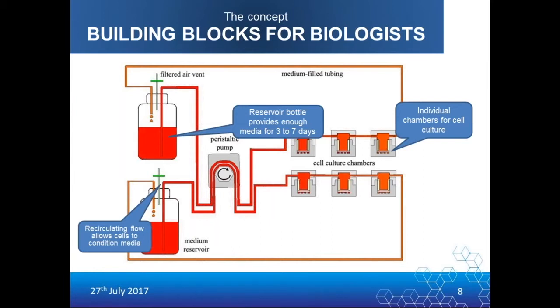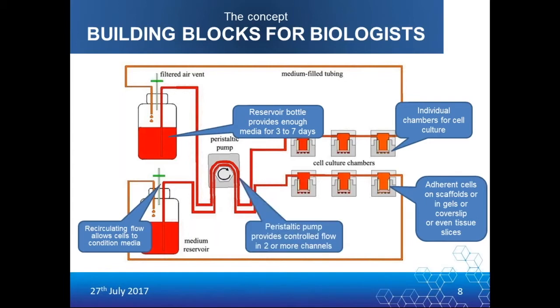These examples have 3 individual cell culture chambers per circuit. The current record for chambers in a row is 12, but the most common we find with our users is 3. In this example, we've got a scaffold being held in the base of the QV500 chamber, but you can grow your cells on cover slips, in gels, and we've even had some users directly placing tissue slices inside the system.